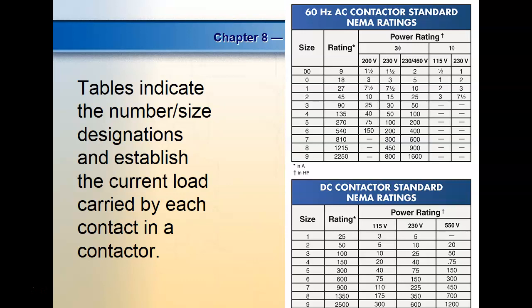What size is this? What size motor can I run on that? So what do y'all think? Jason, what do you think? What size motor could we run on that one? What's the horsepower? What's the voltage? We're running on 208. So what could we run? Up to a 1.5 horsepower motor. We're running three-phase, right?